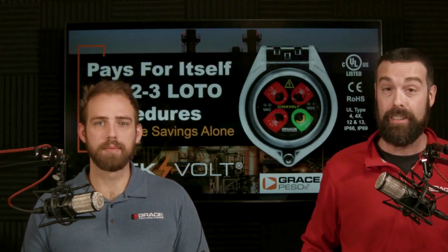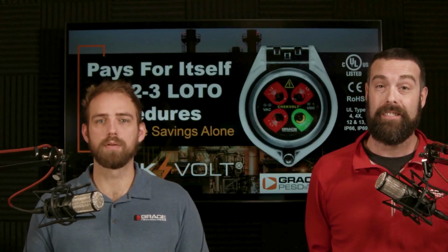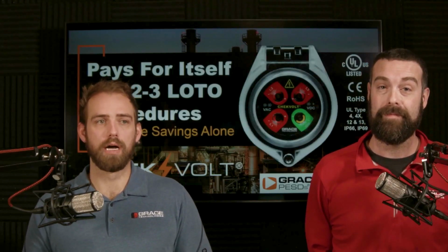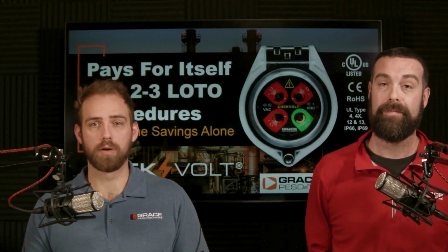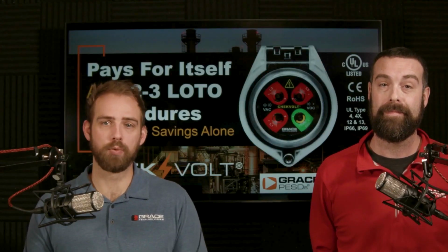Sometimes, and not just with this vehicle, with other vehicles too, these batteries aren't always accessible with both feet on the ground to confirm dead. So with our ChekVolts, whether it's the 3000 volt DC or our 1 kV versions with the 8 feet leads, we can attach to the point of work where these batteries are to confirm dead, and bring the device to where you can have both feet safely on the ground to confirm dead, doing your phase to phase to ground test.